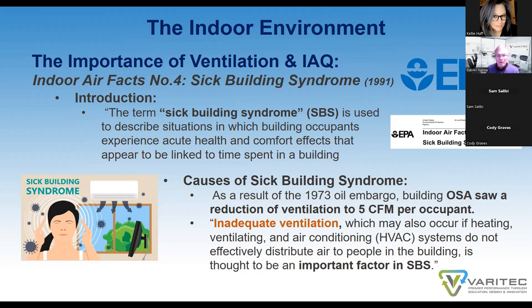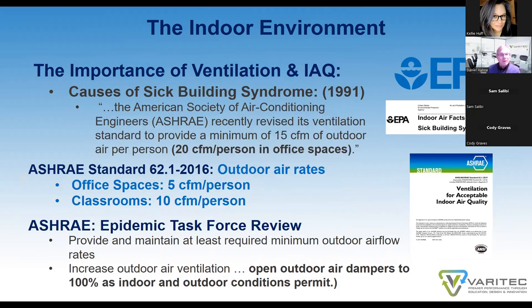Inadequate ventilation, however, it was discovered, may cause problems when heating, ventilating and air conditioning systems do not effectively distribute air to people in a building. This is thought to be an important factor of SBS, or sick building syndrome. So, not having adequate ventilation, not having adequate outside air into a building. And at those levels, the CFM of outside air provided to a building was based on a level of 5 CFM per occupant.